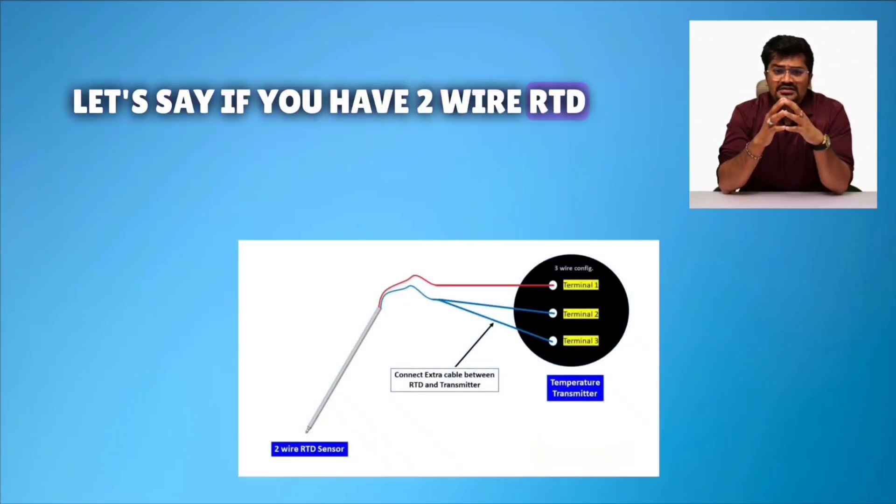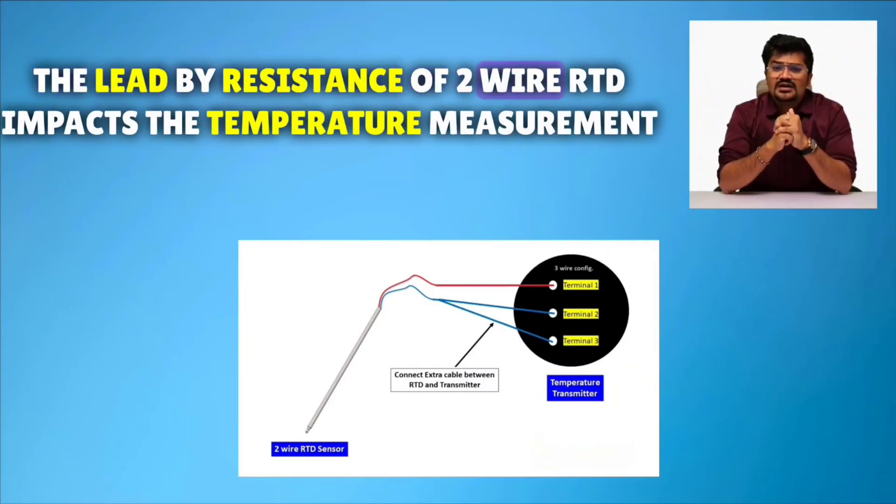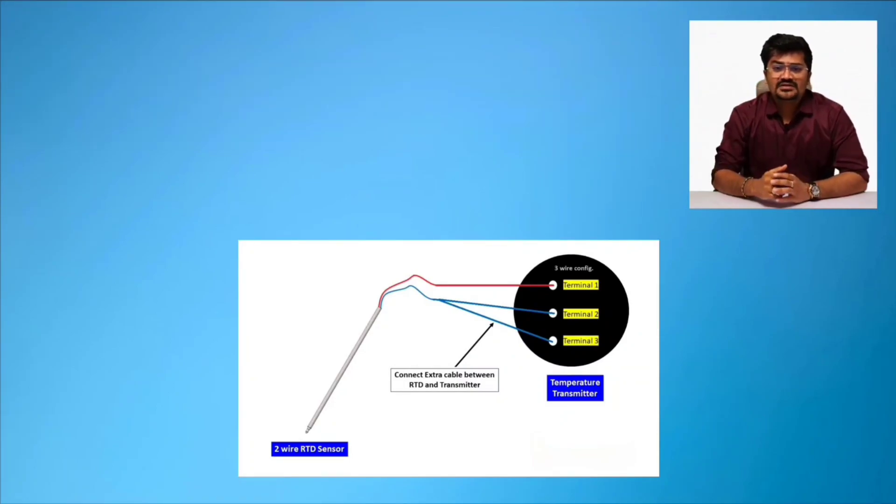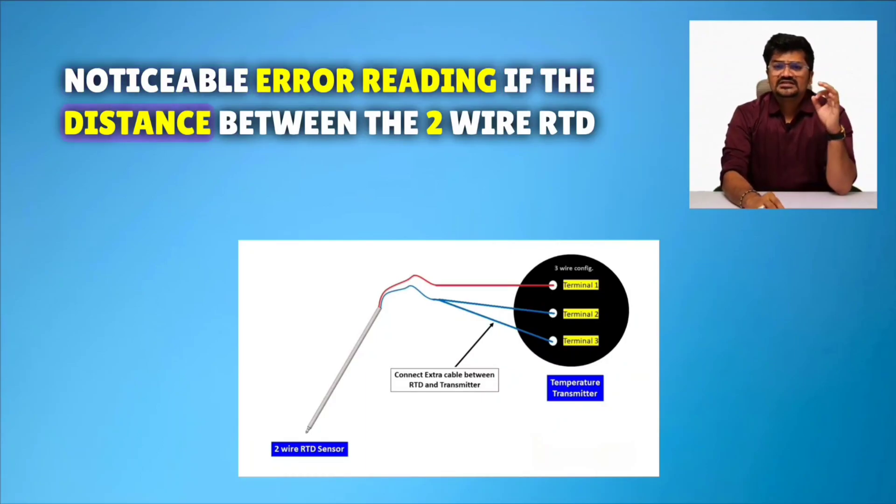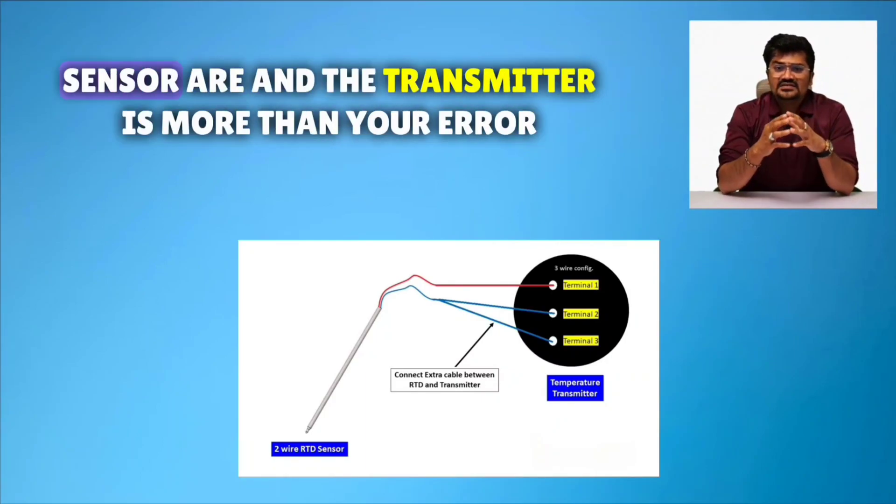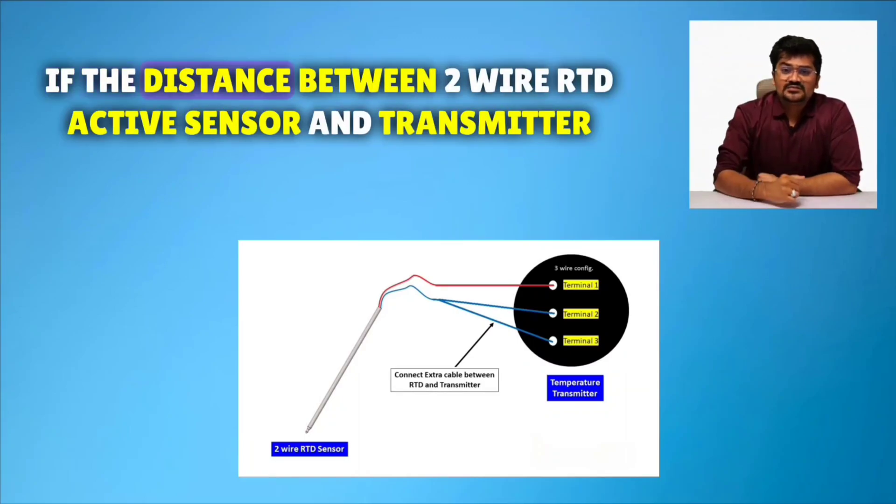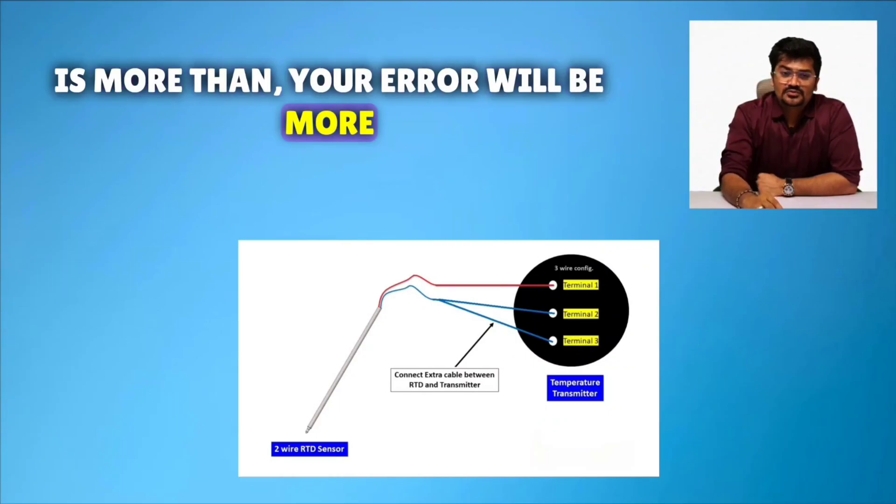Let's say if you have 2-wire RTD, the lead wire resistance of 2-wire RTD impacts the temperature measurement and creates noticeable error reading. If the distance between 2-wire RTD sensor and transmitter is more, your error will be more.